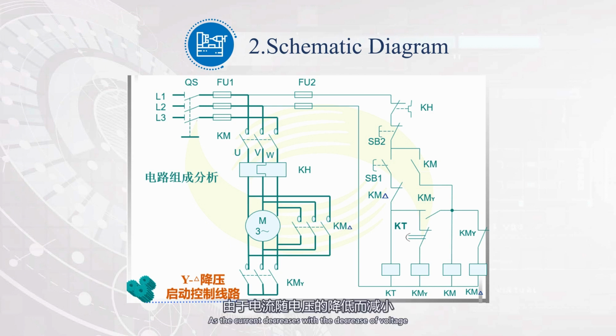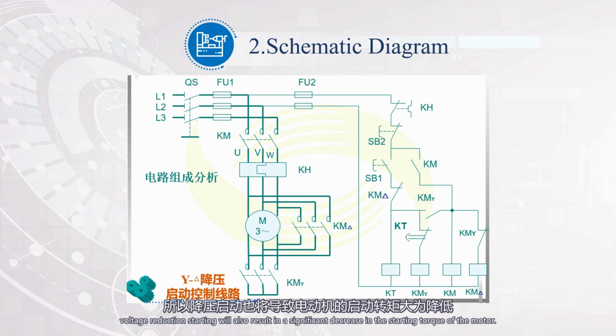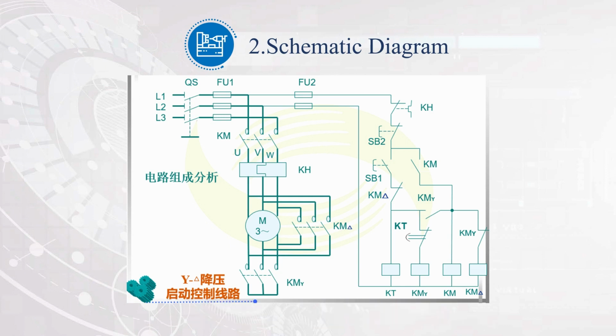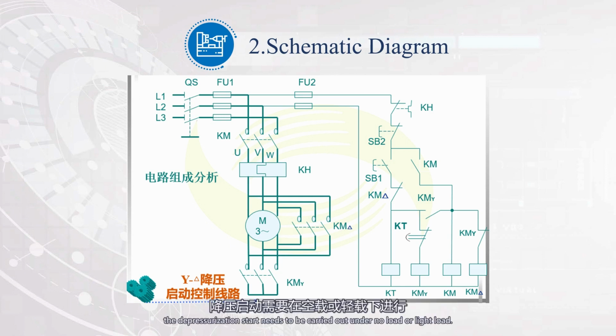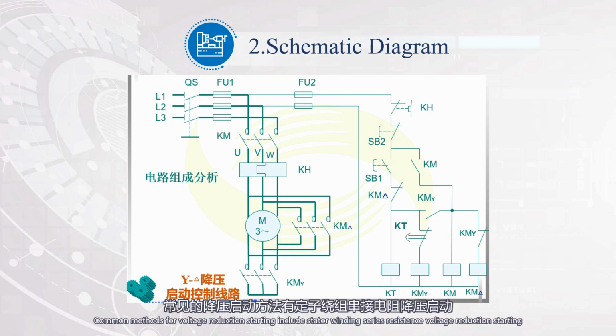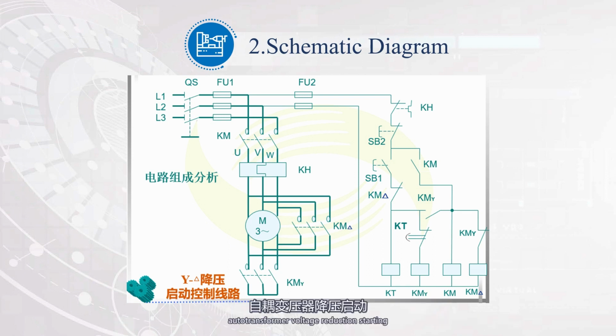As the current decreases with the decrease of voltage, step-down starting achieves the goal of reducing the starting current. However, as the torque of the motor is proportional to the square of the voltage, voltage reduction starting will also result in a significant decrease in the starting torque of the motor. Therefore, the depressurization start needs to be carried out under no load or light load. Common methods for voltage reduction starting include stator winding series resistance voltage reduction starting, autotransformer voltage reduction starting, Y-delta voltage reduction starting, soft starter voltage reduction starting, etc.